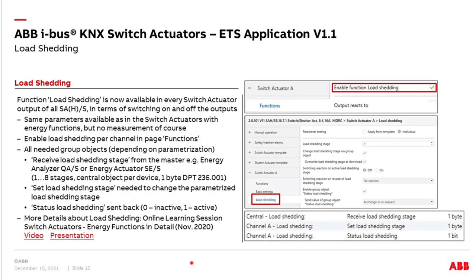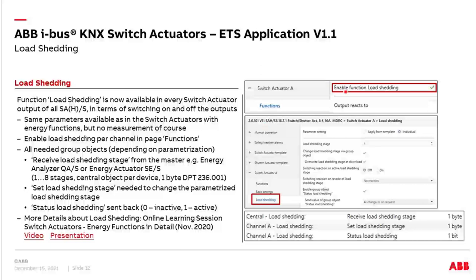Let's look at the parameters. In all the components, you enable the load shedding function under Functions at the output — for example Output A — and then you get a collection of the typical parameters you need to adjust. Of course, also dedicated group objects handle the load shedding solution. The principle is a one-byte object that receives the load shedding stage number which has to be turned off. In the output you assign which shedding stage belongs to that output — in my case, stage one. You can also change the shedding stage telegram if needed.